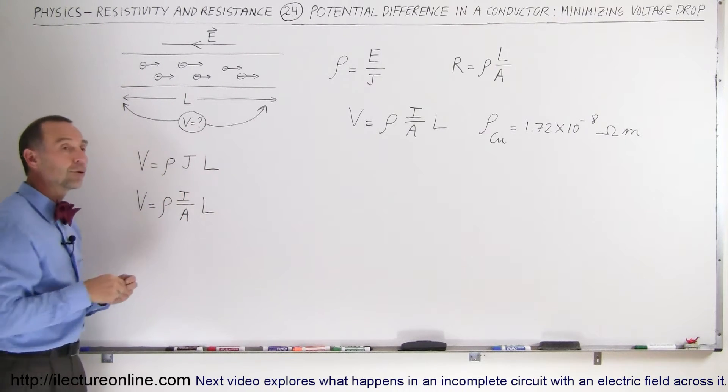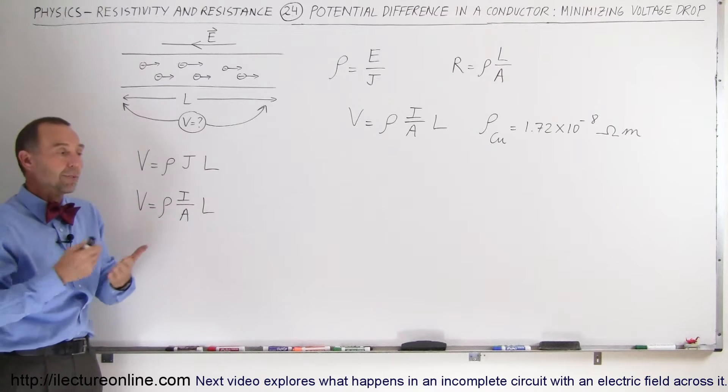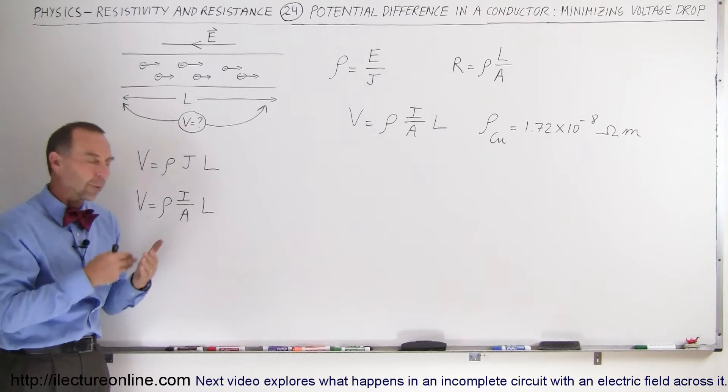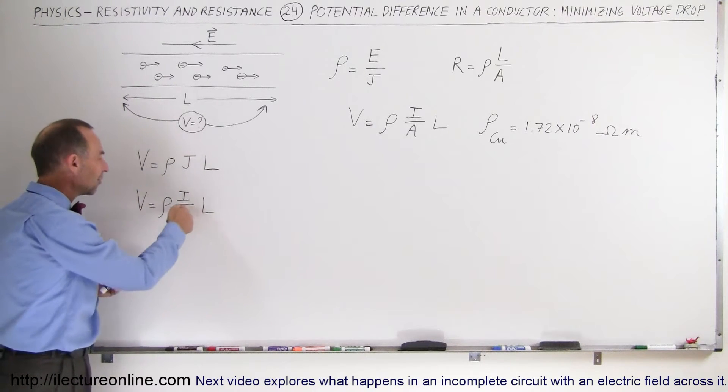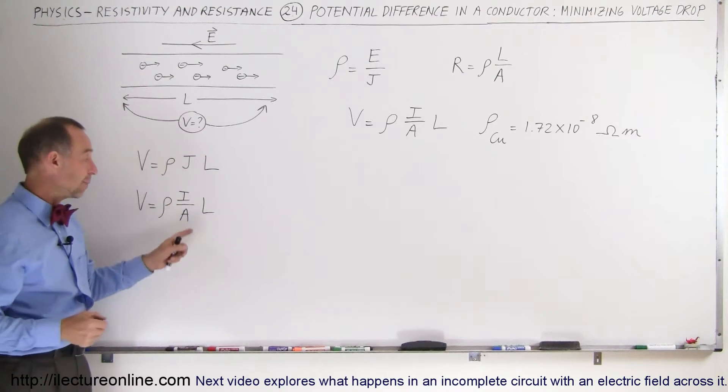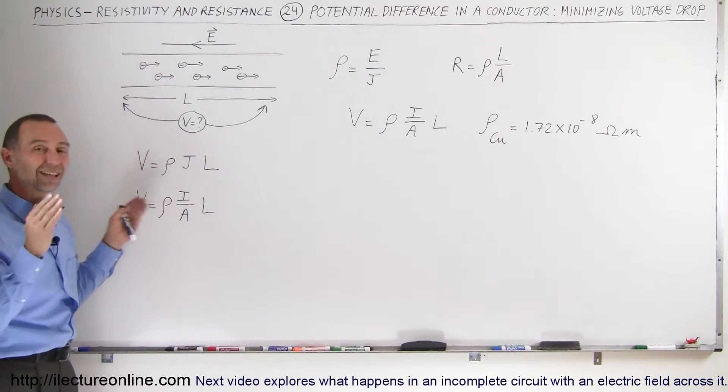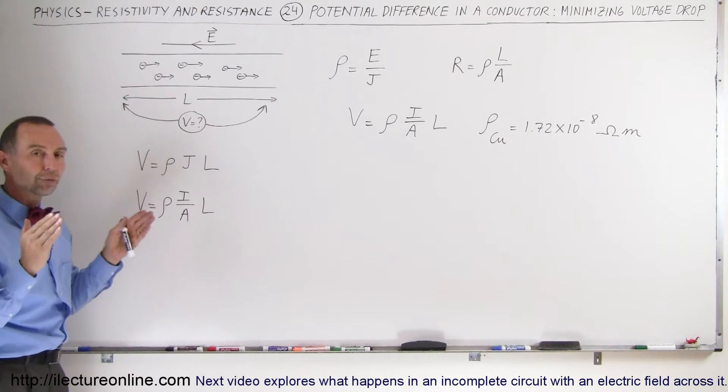Notice the only component here in the denominator is the cross-sectional area. We may not be able to do anything about the current requirement. We may require a certain amount of current to go through the wire. So the only control that we have is the cross-sectional area of the wire. If we make that bigger, we have a smaller potential difference across the wire, a smaller voltage drop.